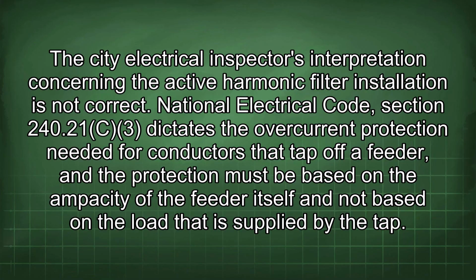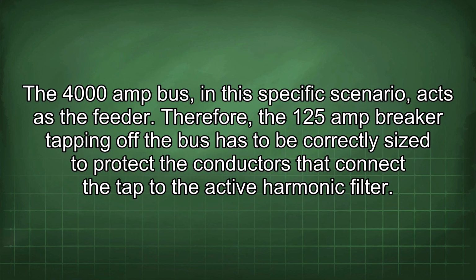City Electrical Inspector's interpretation concerning the active harmonic filter installation is not correct. National Electrical Code, Section 240.21(C)(3) dictates the overcurrent protection needed for conductors that tap off a feeder, and the protection must be based on the ampacity of the feeder itself and not based on the load that is supplied by the tap. The 4000 amp bus in this specific scenario acts as the feeder.